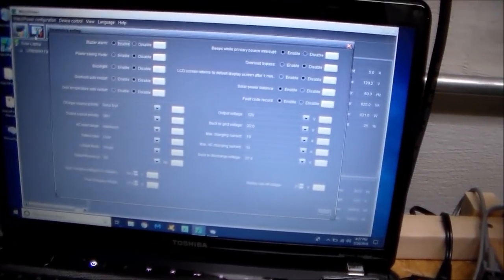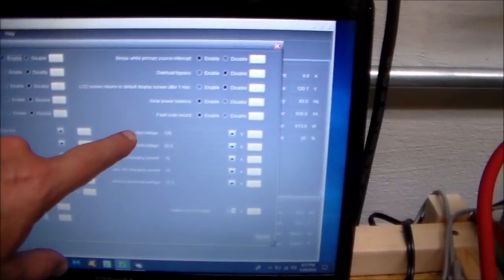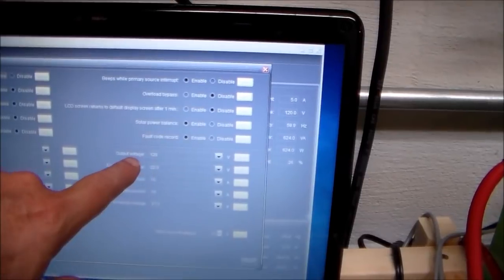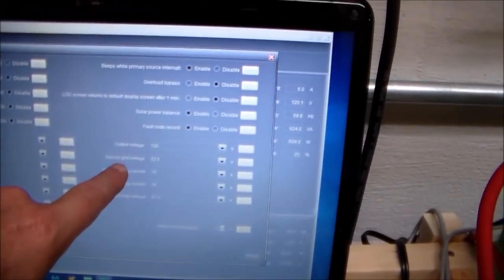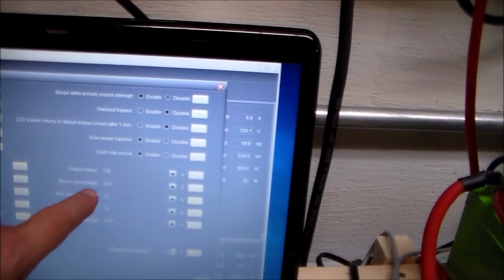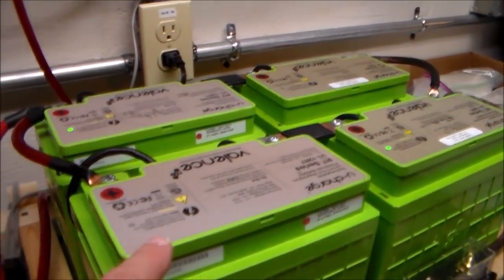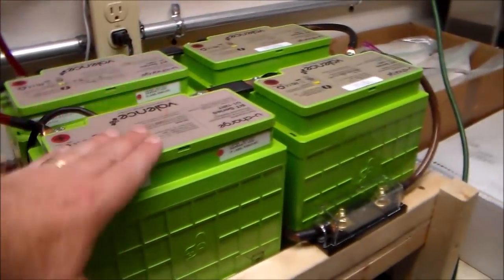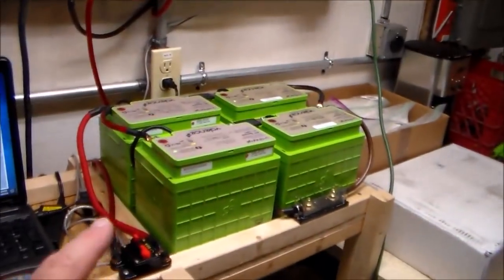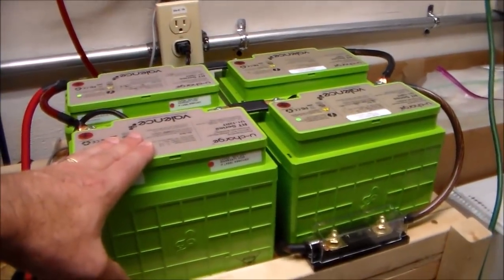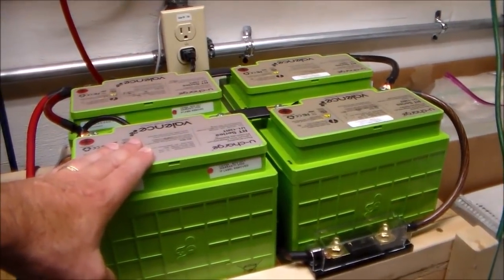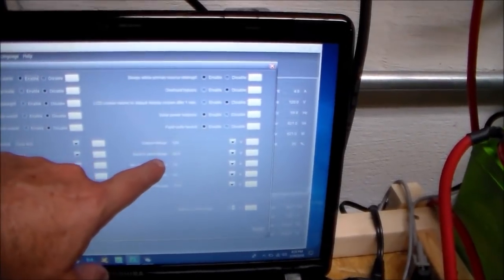I'm not going to get into this too much because your particular situation may be different depending on the batteries and solar panels you have. In the US we use a 120 volt system, so that's what this is set to. I've got it set at 22 volts for my back-to-grid voltage. That means if the batteries ever drop to 22 volts, on this 24 volt system I've configured, it'll automatically switch back to the grid. I can drain these batteries totally if I want, but I'm not going to do that.